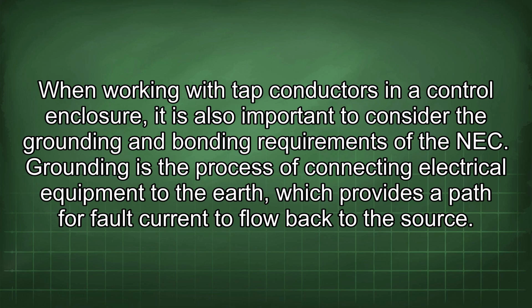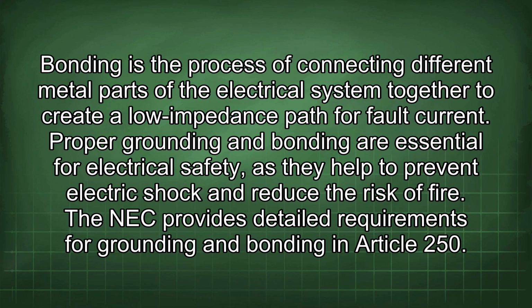When working with tap conductors in a control enclosure, it is also important to consider the grounding and bonding requirements of the NEC. Grounding is the process of connecting electrical equipment to the earth, which provides a path for fault current to flow back to the source. Bonding is the process of connecting different metal parts of the electrical system together to create a low impedance path for fault current. Proper grounding and bonding are essential for electrical safety, as they help to prevent electric shock and reduce the risk of fire.